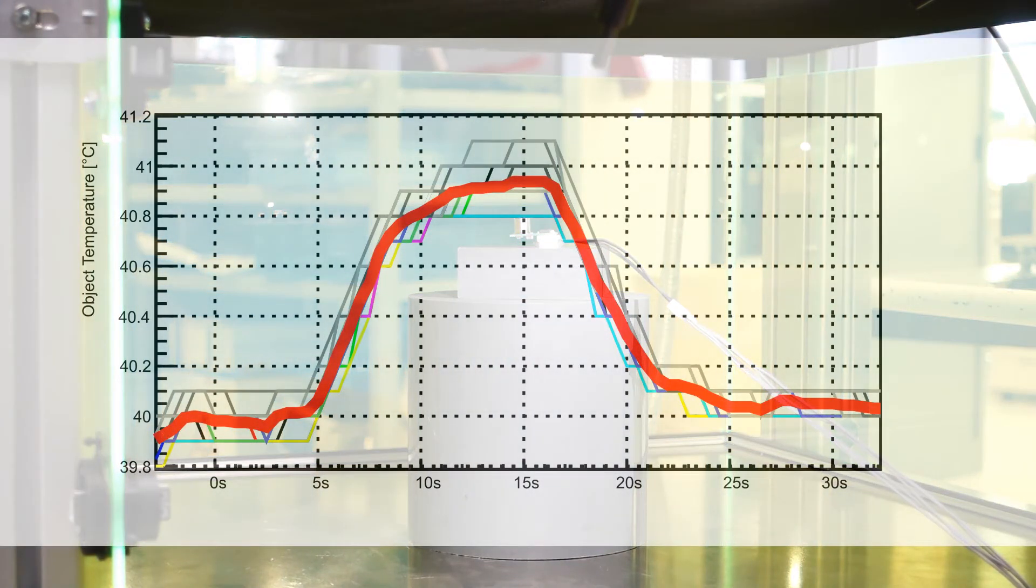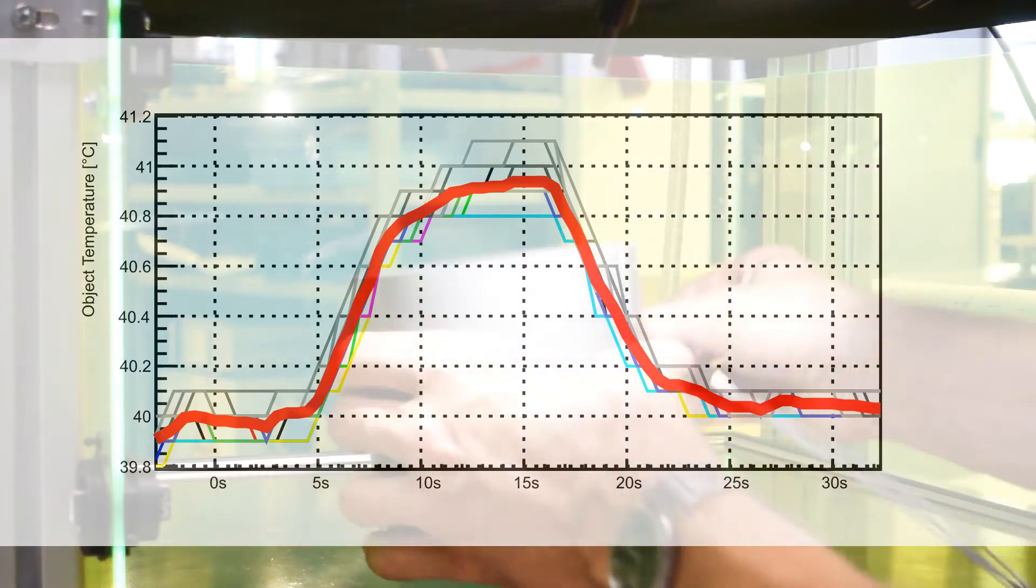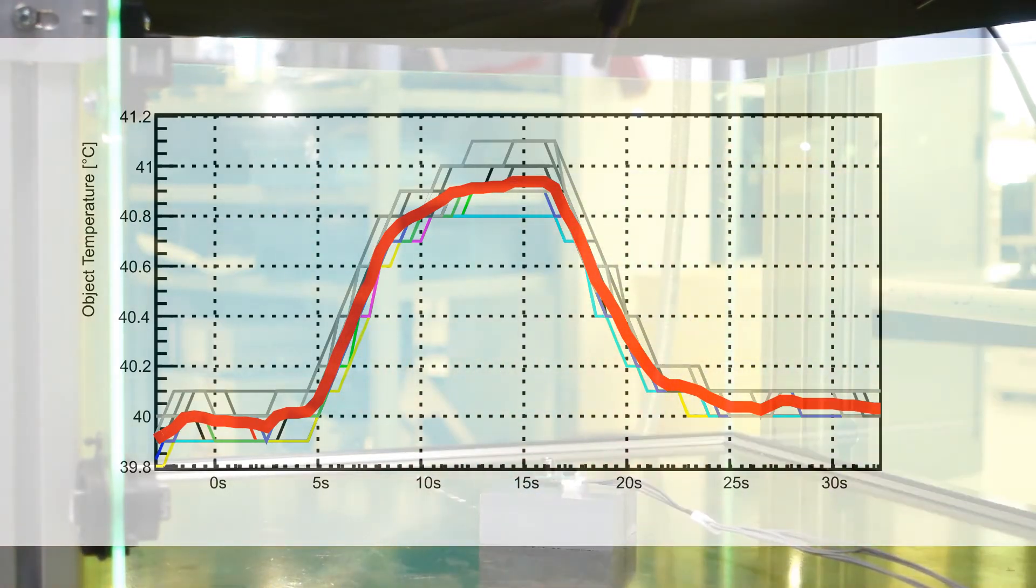The mean temperature over all pixels is shown here as a red line. It starts with a reading of 40 degrees C and increases to almost 41 degrees C when we reduce the distance to the blackbody.